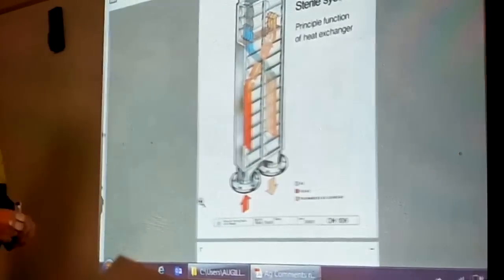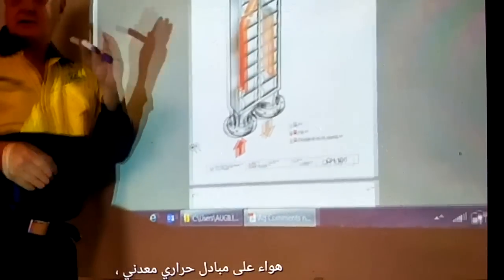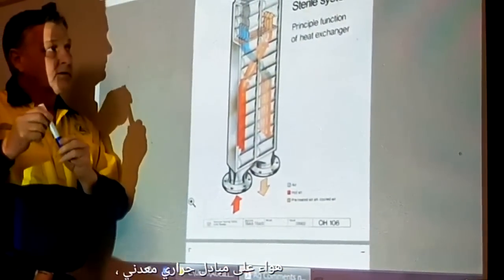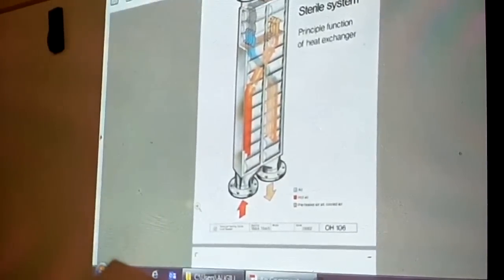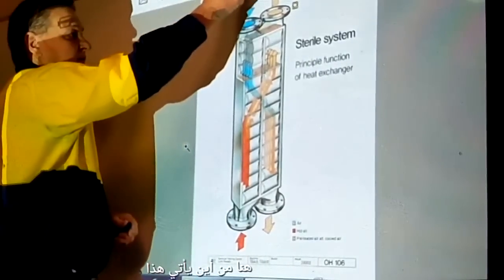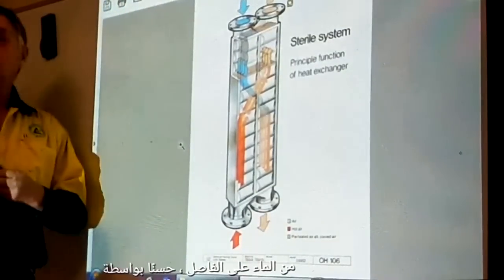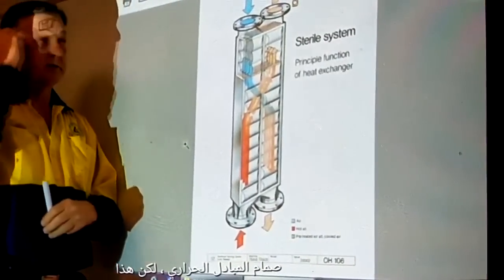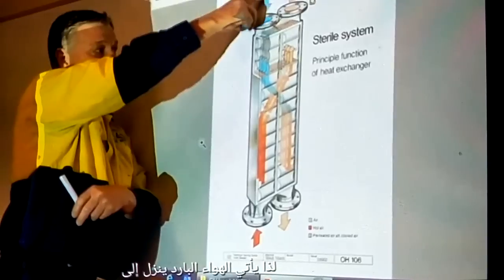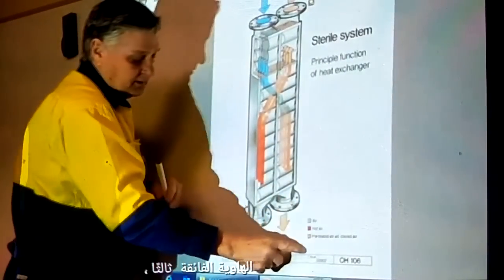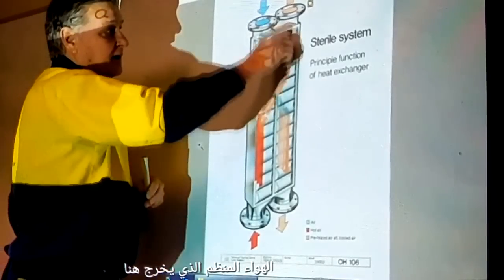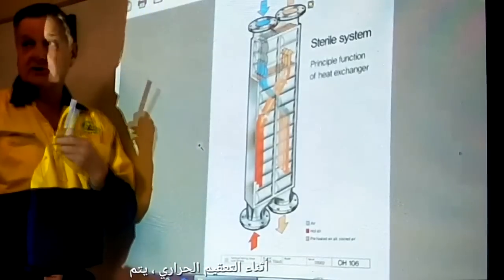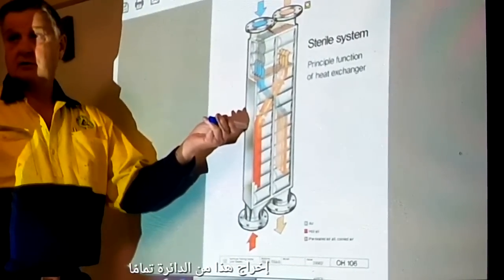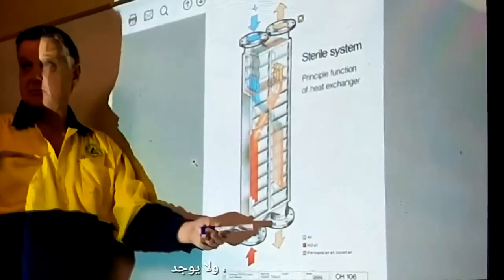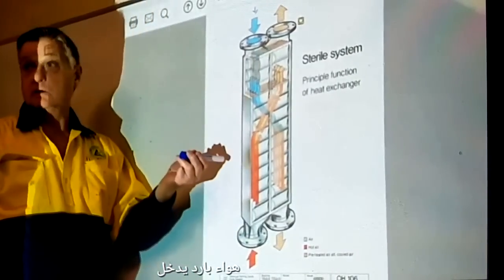Then we have the heat exchanger. The heat exchanger is an air on metal heat exchanger. So we have the inlet here. This is coming from the water separator. So cold air coming in, going down to the superheater, then out of the superheater, and then regulated air going up here. During heat sterilization, this is taken out of the circuit completely. You have bypass, going to the water separator and out. There's no cold air coming in during heat sterilization.